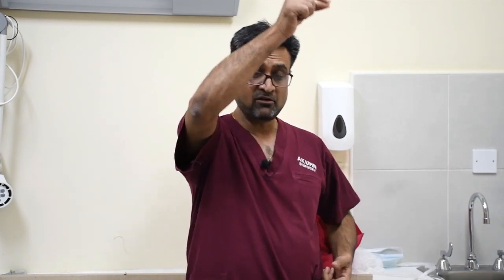So please understand one principle here, that when you want to place this return electrode and when you are doing surgery, please understand that monopolar, whenever it gets concentrated into a thin spot, will cause a burn there. Now that is practical in 2-3 areas. Number one, where you apply the return electrode. Number two, where you're operating. So for example, there is a band of adhesion that is attached to the surface, to the abdominal wall. So that band of adhesion may be a thin strip of band, but the band is now touching a bowel loop down there. So what will happen when you activate this?